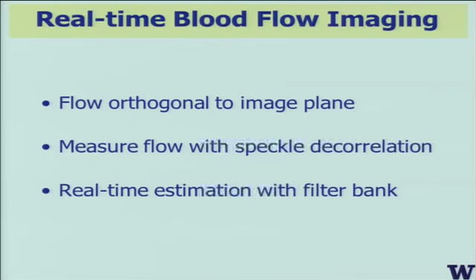So there were multiple things that you can do with an array that you can't do with a wobbling single element transducer. I'll give you one of these, but there's a host of these that can be done. And one of those is real-time blood flow imaging while you're in situ, inside a coronary artery. And it's an interesting geometry, because you can't do Doppler, which is a normal blood flow imaging system. It has a Doppler effect where the motion is along or against the propagating beam. I'll show you in a second. You're exactly orthogonal in this geometry. But because you have arrays, you can do some decorrelation measures. That is, you can watch blood as it goes by and watch the change in the image characteristics to quantify flow. And because it's an array, you can do real-time estimation with that.